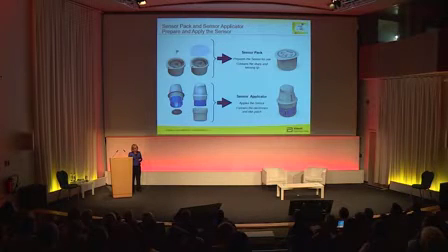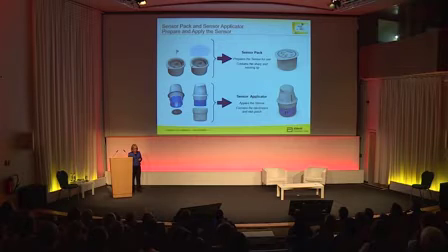The sensor pack and sensor applicator prepare and apply the sensor. So the sensor pack prepares the sensor for use, and it contains the sharp and the sensing tip, which sits in the interstitial fluid. The sensor applicator applies the sensor, and it contains the electrodes and the skin patch.